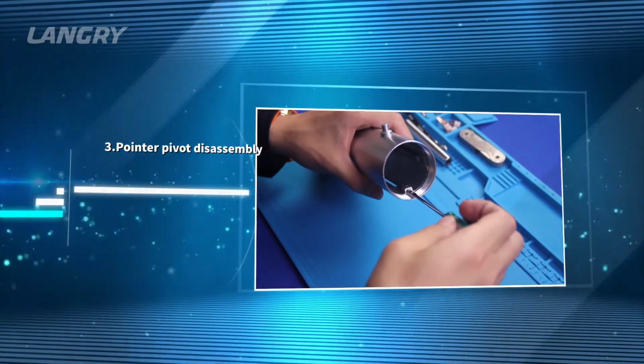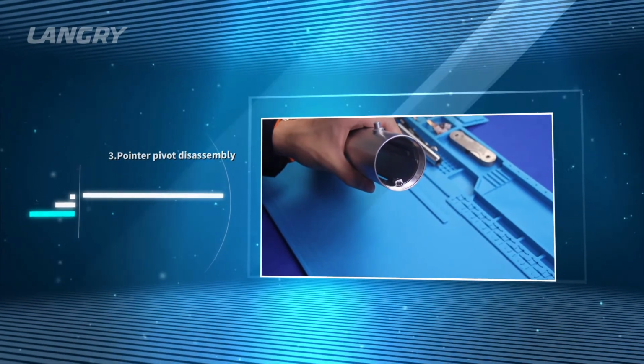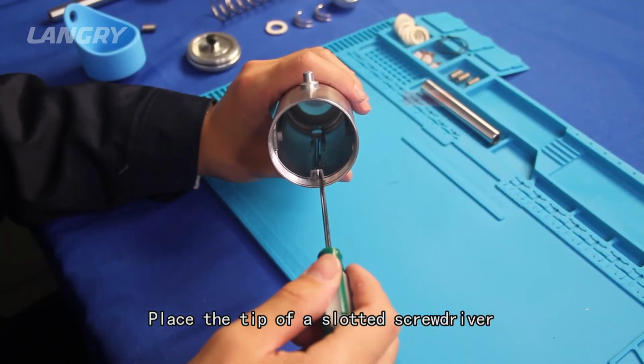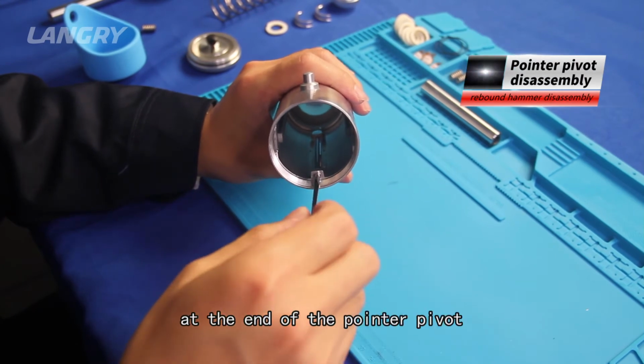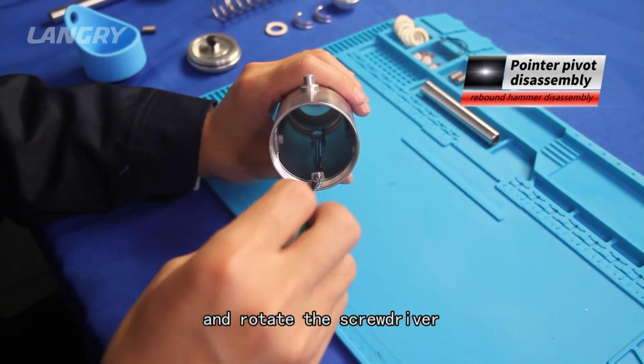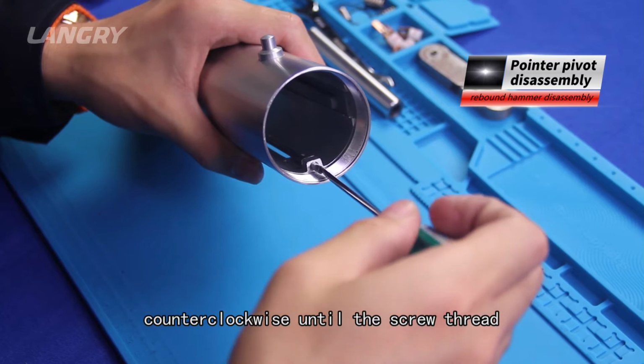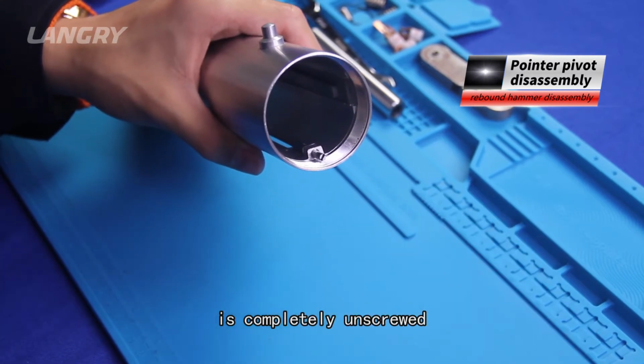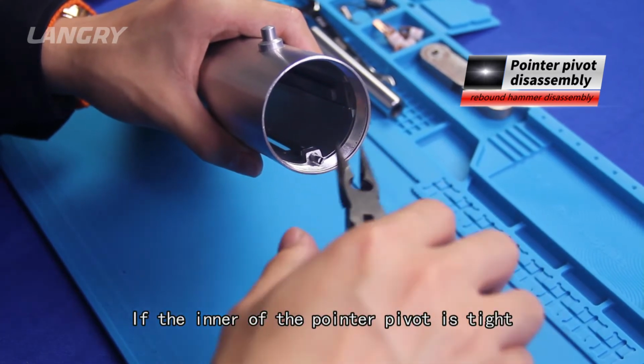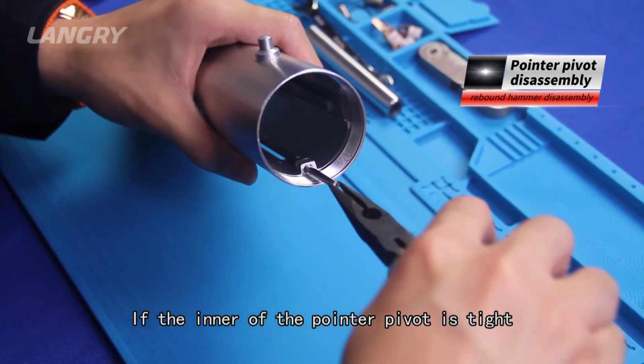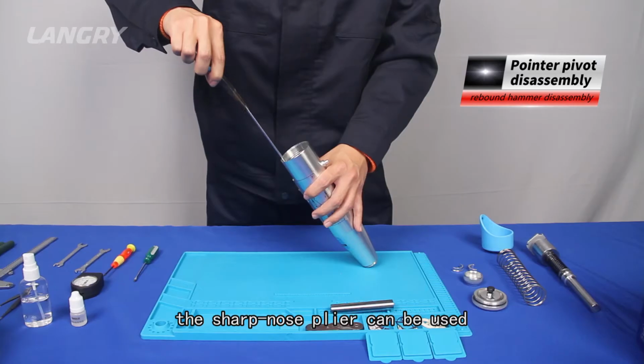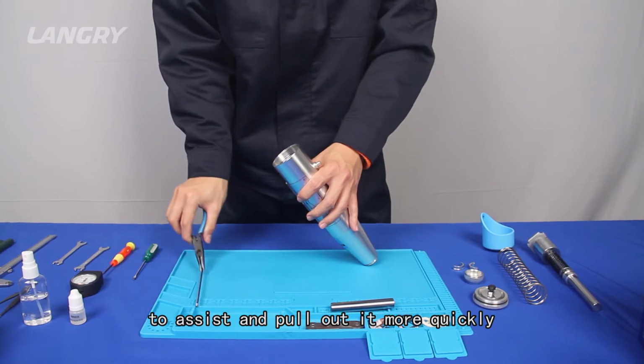3. Pointer pivot disassembly. Place the tip of a slotted screwdriver in the groove at the end of the pointer pivot and rotate the screwdriver counterclockwise until the screw thread is completely unscrewed. If the inner of the pointer pivot is tight, the sharp nose plier can be used to assist and pull it out more quickly.